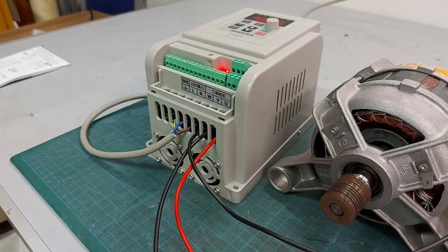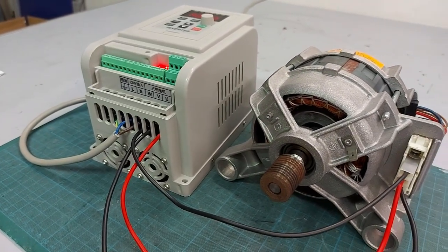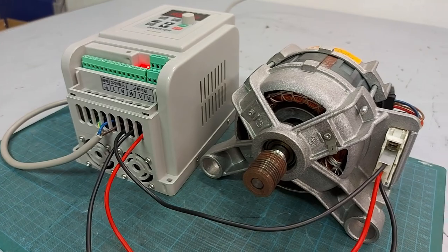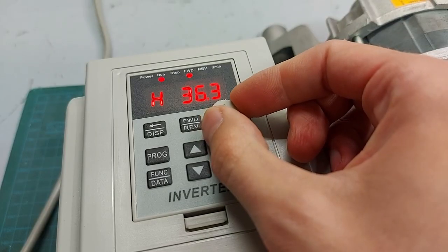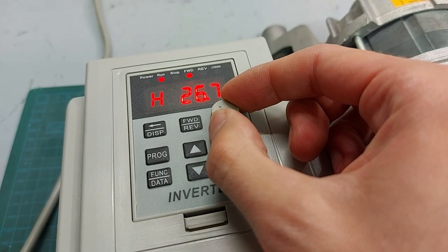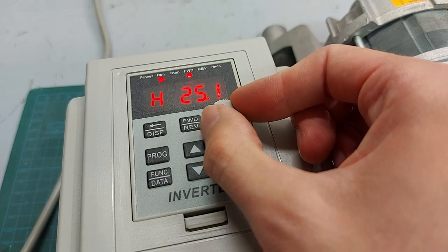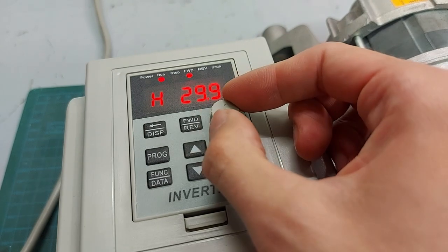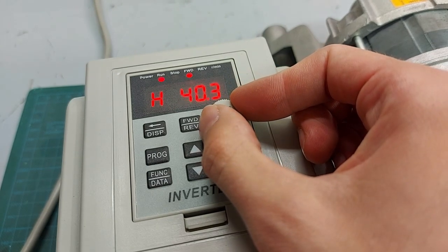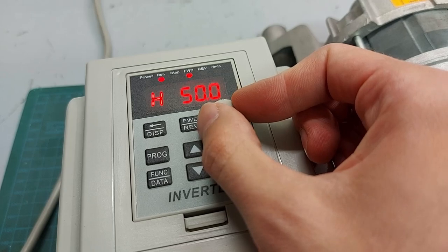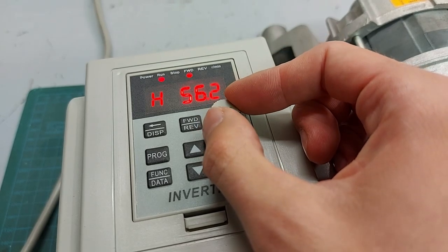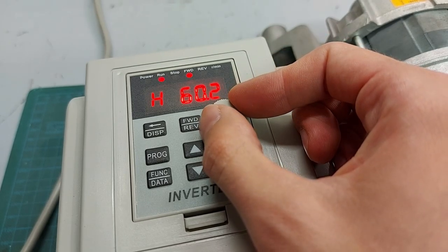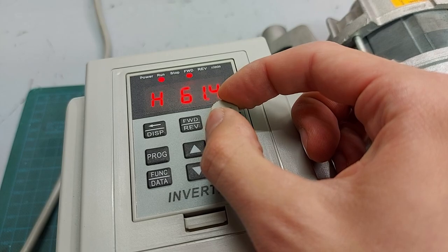This type of inverter called variable frequency drive works by fixing the amplitude of the sinusoidal waves and acting on the frequency to adjust the motor speed. In particular, if the frequency increases, the motor speed increases as well, because it increases the angular velocity of the rotating magnetic field in the stator.